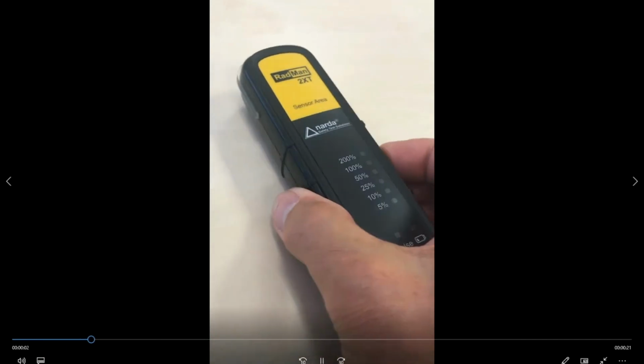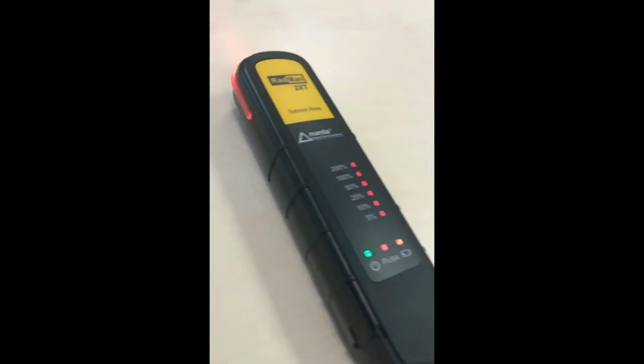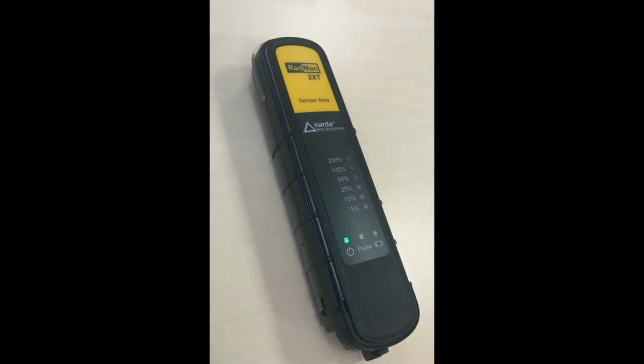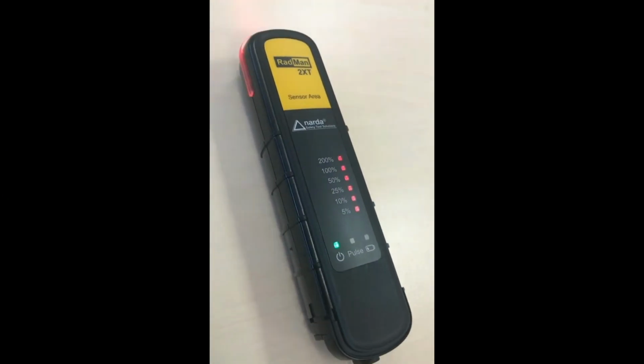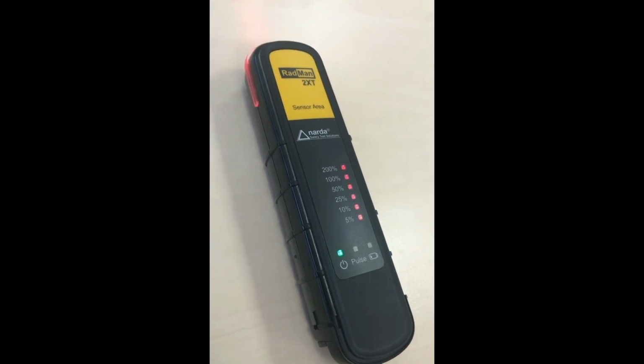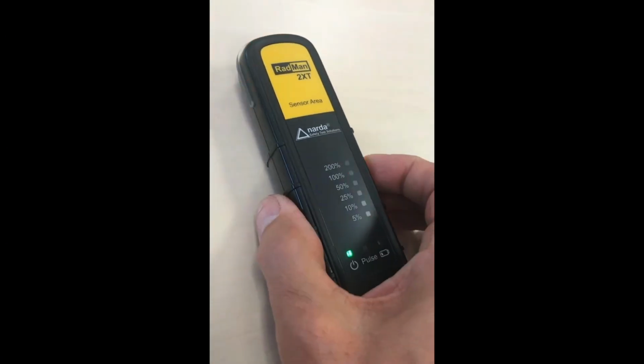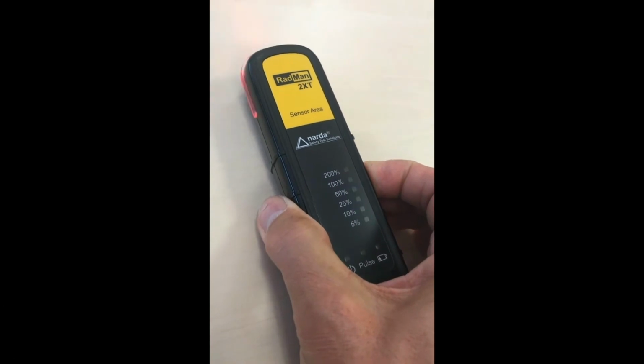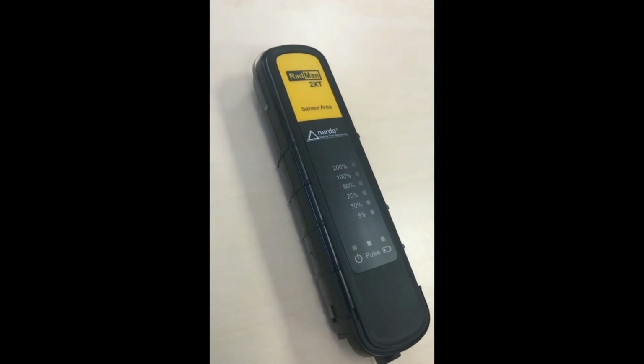Here's a quick video showing the sensor fail test when you switch on the instrument. If there is a failure, the instrument will not measure - it will provide constant alarms, all LEDs flashing, and it's impossible to operate the unit because it won't finish booting or starting. So you can be 100% certain if there's a failure in the instrument, in these six sensors, such as an open circuit.